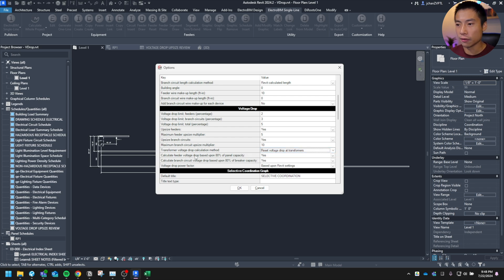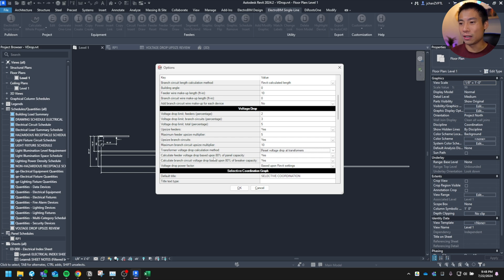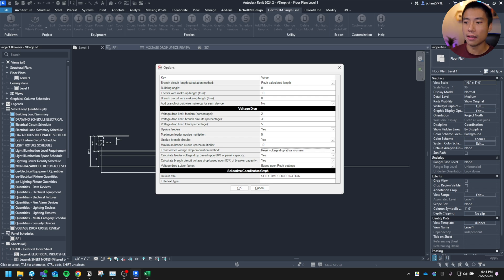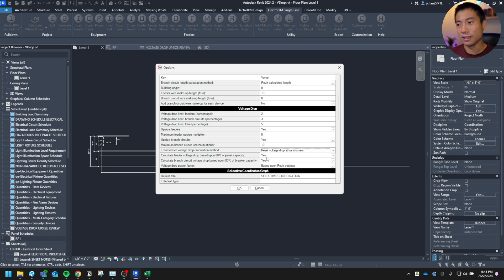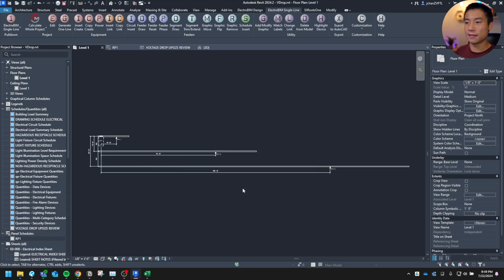And then down here, these are the two features that I really love. You can calculate the voltage drop based on 80% of panel capacity. And then here's the other one. Branch circuits can be calculated at 80% of breaker capacity. So I turned those two onto yes. And what it'll do is put the 80% of the breaker or panel capacity into the voltage calc and run the calculations to get your proper wire size. So let's see what that does.